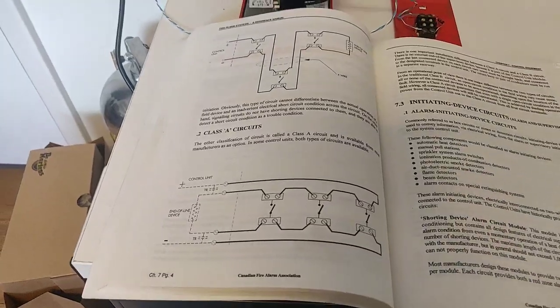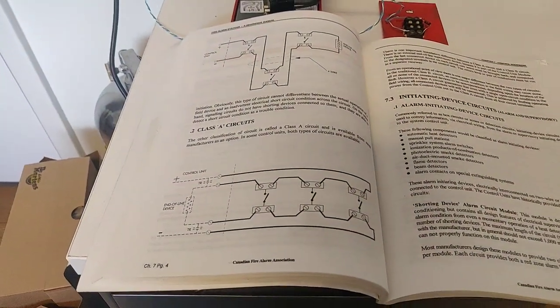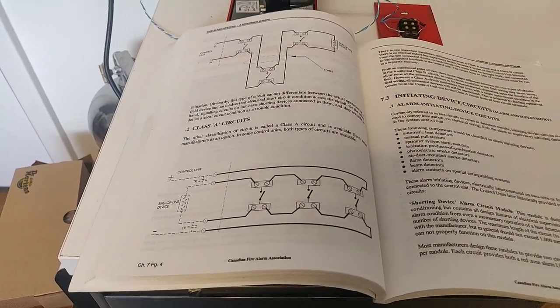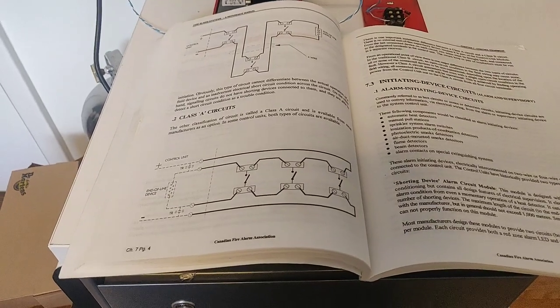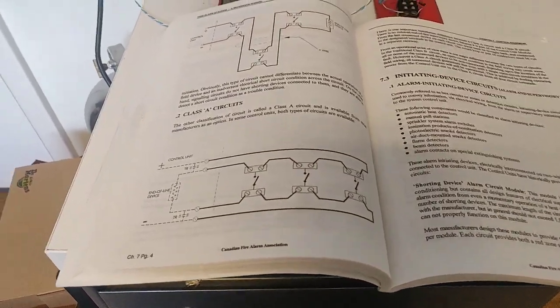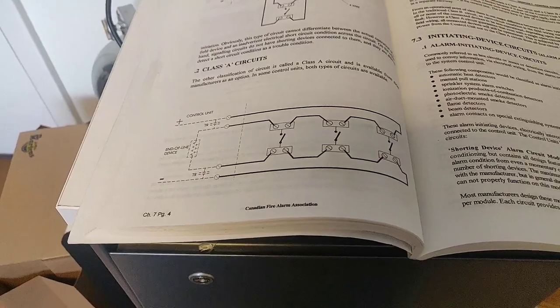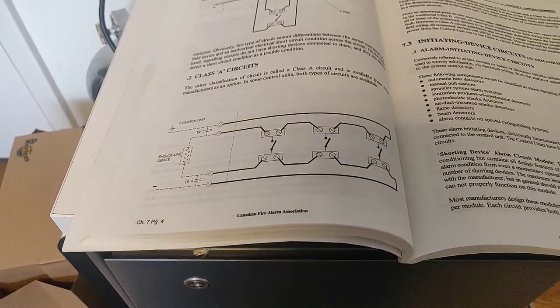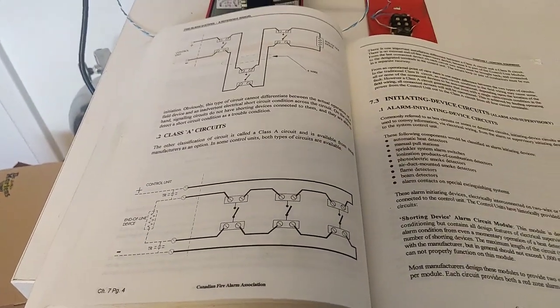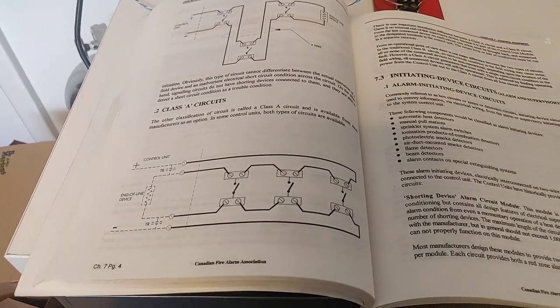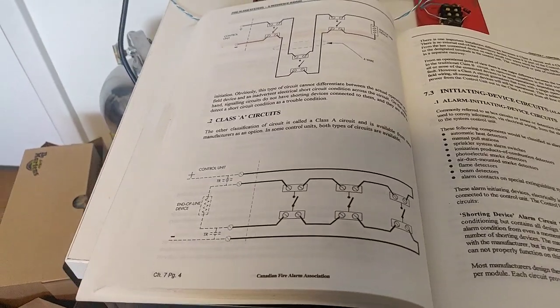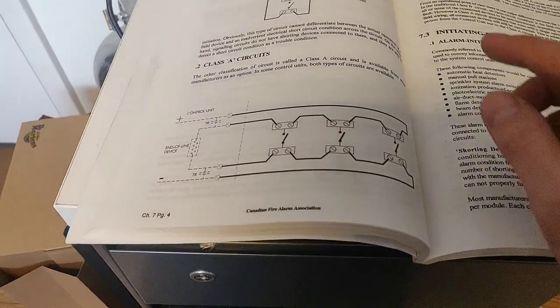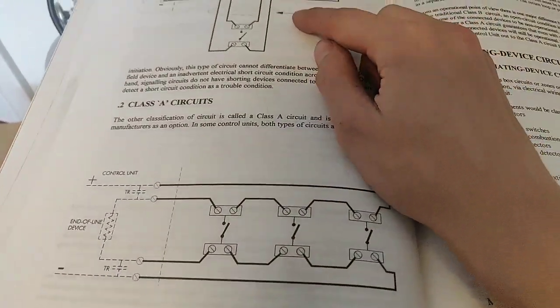So I think it's imperative that I take a minute to go over some theory here, just so that we're all on the same page of what we're talking about. There's two schemes in which you can wire a fire alarm circuit: there's class A and class B in a conventional system. We're not talking about addressable here—that's a whole other story.